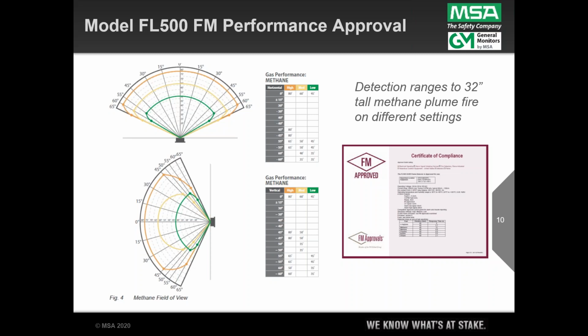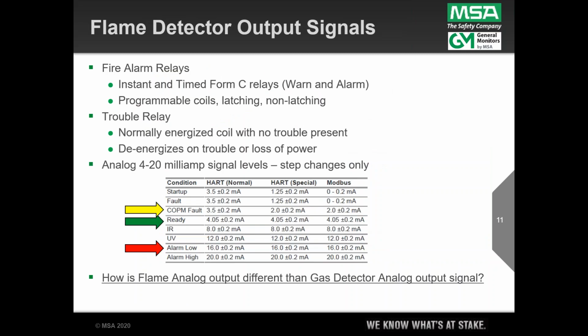And so, again, we were talking about this, that as long as you're not looking for more than 80 feet of coverage, and in most cases 60 or even 45 is going to be adequate, we think that's a great place to start with this instrument for most applications. So I want to take a minute to just talk about the type of signal outputs from our flame detectors, and that's what the next slide here represents.